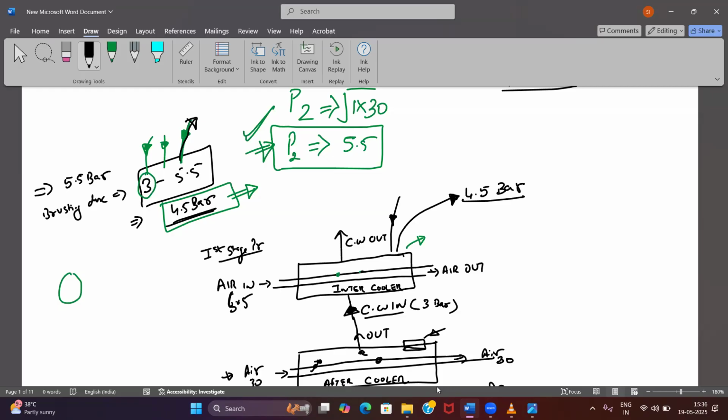Agree? Yes, sir. Again, leakage happened and the compressor burst. The jacket, this cooler completely burst out. It shattered into pieces. 30 bar is not a small pressure. Agree? Yes, sir. And your coolers are not thick enough to handle this pressure. That's why, आप देखो, bursting pressure कितना है. It is very less.